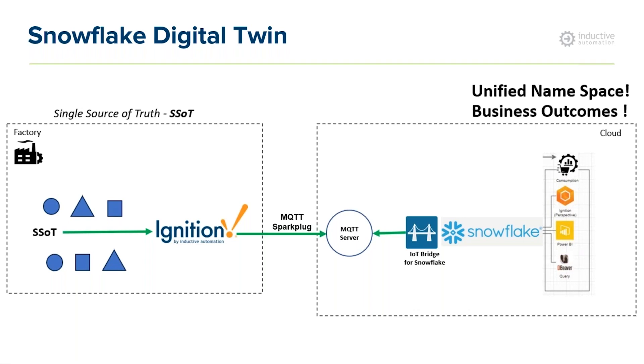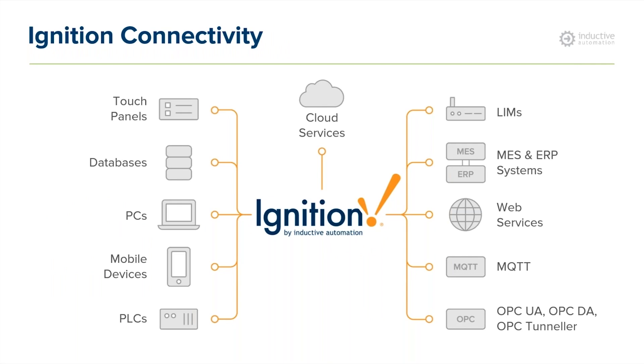The first step in this journey is to connect and model the data that's on-premise using the Ignition platform. Ignition is server software that acts as a hub for everything on the platform to achieve total system integration. We can connect to any PLC using native drivers for all major PLCs, and we can also communicate over OPC UA — connecting to devices that support it directly or through third-party OPC servers. Essentially, we can bring in any kind of data from the OT world into Ignition.